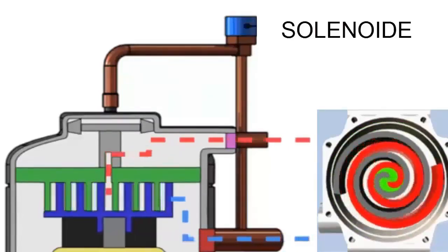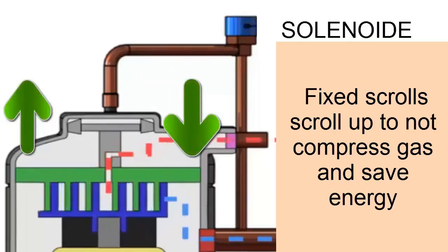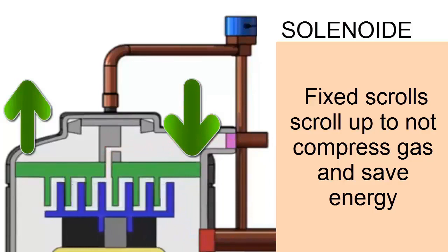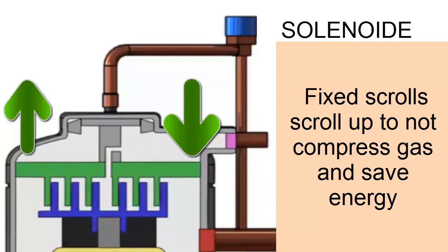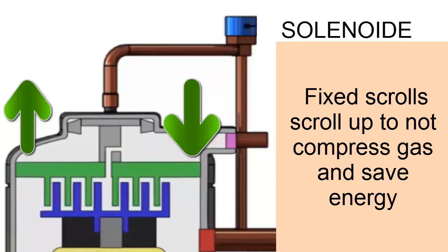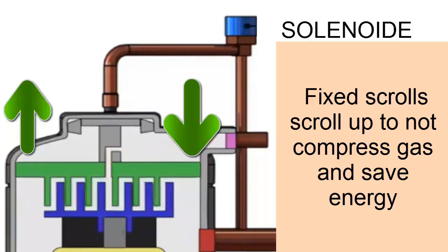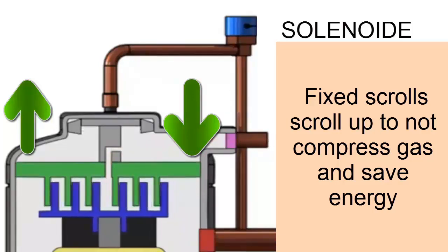Observing the animation that we are showing on the screen, we can notice that at times when the cooling capacity of the compressor exceeds the need of the premises, then the separation of the spirals occurs vertically. This separation is caused by a solenoid. In addition, we can notice that although the spirals separate, the motor does not stop, avoiding unnecessary starting peaks.